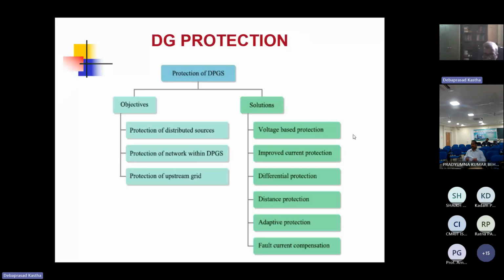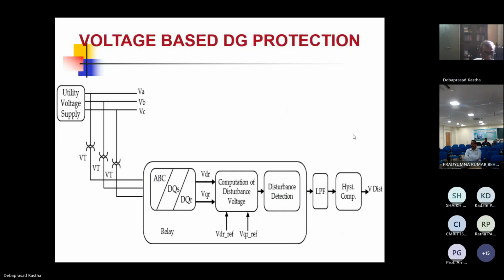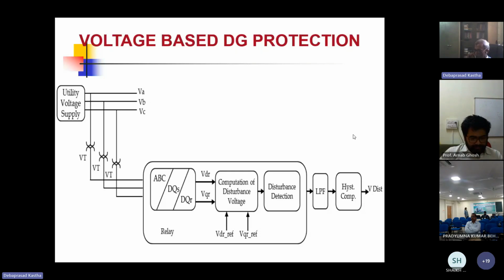So when you come to protection schemes for distribution networks where distributed generators are present, you will have to think differently. In fact, the distribution protection system that was used for the traditional power system will not work. You have to bring in some amount of the protection philosophy that is used for transmission lines. Other than that, there are other ways to do it. Now, when a DG limits its output current, it does so by reducing the output voltage. In fact, the output voltage can get distorted also. So instead of just current-based protection, people are also thinking about measuring the voltage and seeing the amount of reduction, based on which you can take a decision on the fault.